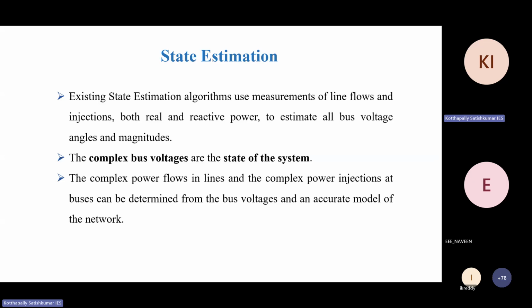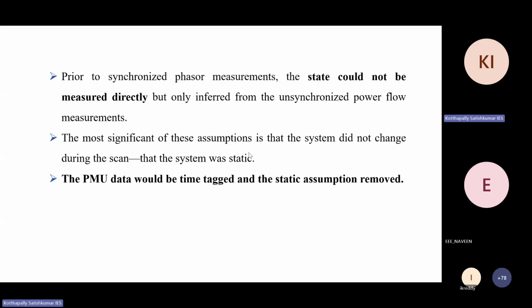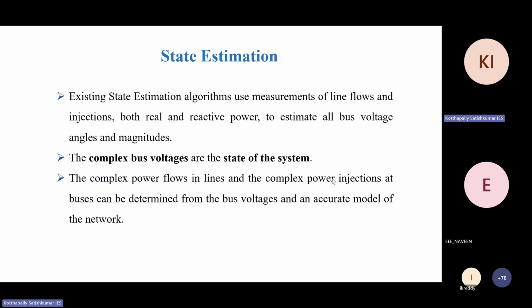But the advantage with PMU, as I told, is that this static assumption itself will be removed, right? You will directly get the linear state estimation. So you will not use these basic algorithms and run them many times. There is no iterative process in PMU because you are directly measuring the state of the system, since you have a common resource, a common GPS signal. That's a common platform. Using that common GPS, you directly measure the system. So there is no calculation of the state of the system.